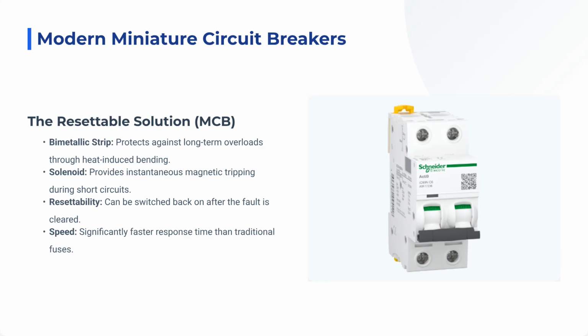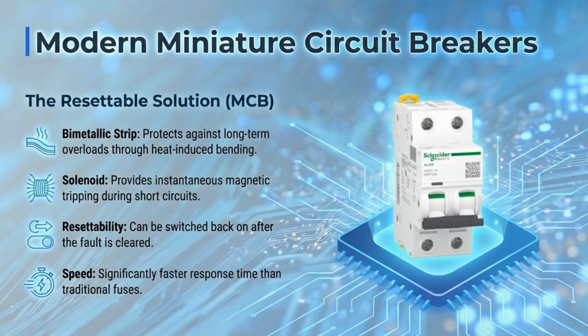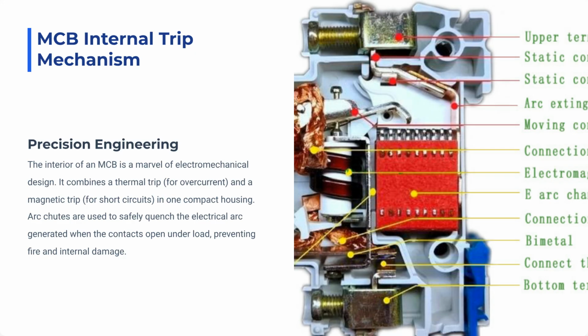Modern miniature circuit breakers, or MCBs, offer a resettable solution. They use a bimetallic strip for protection against long-term overloads and a solenoid for instantaneous short-circuit tripping. The key benefits of an MCB are its resettability after a fault is cleared and its significantly faster response time compared to traditional fuses. Inside the MCB is a precise electromechanical design that combines thermal and magnetic trip mechanisms. Arc chutes safely quench the electrical arc generated upon tripping. This precision engineering allows the MCB to efficiently protect devices and wiring from damage caused by excessive current.